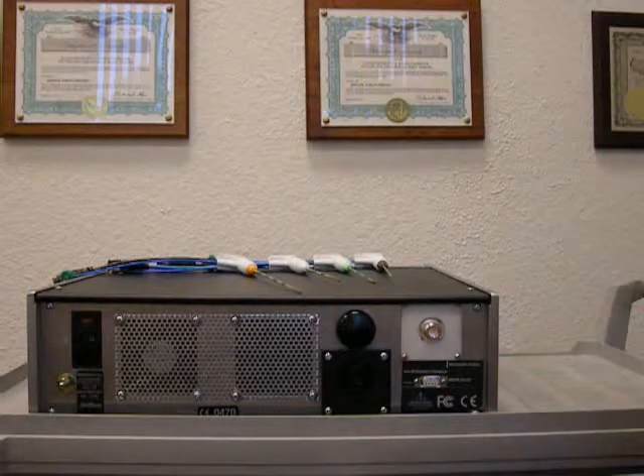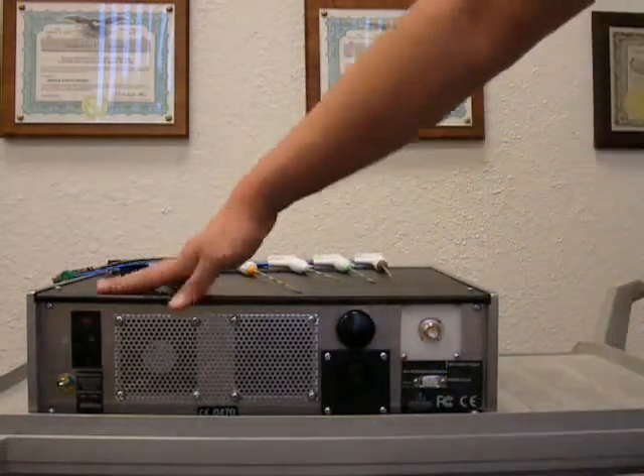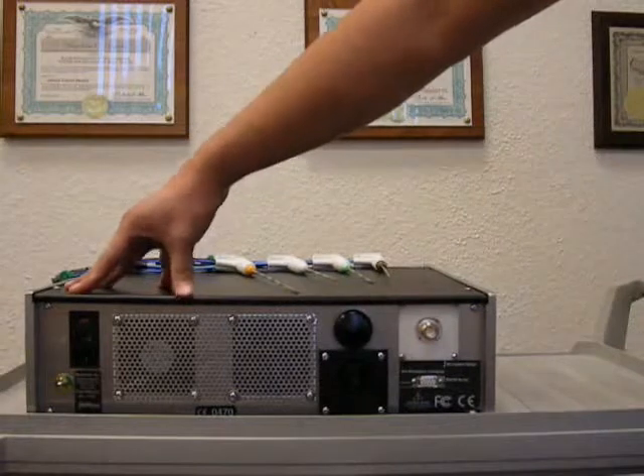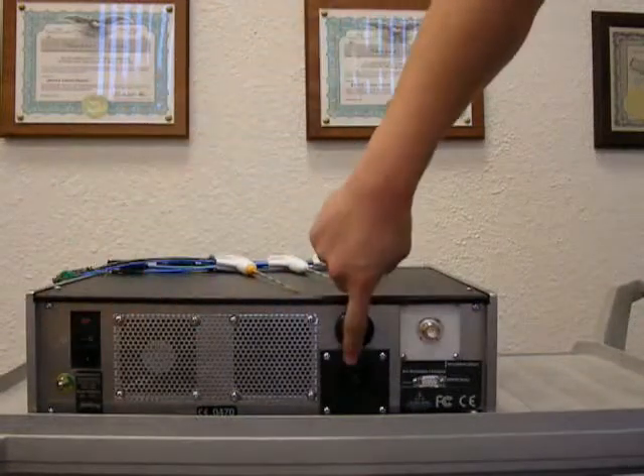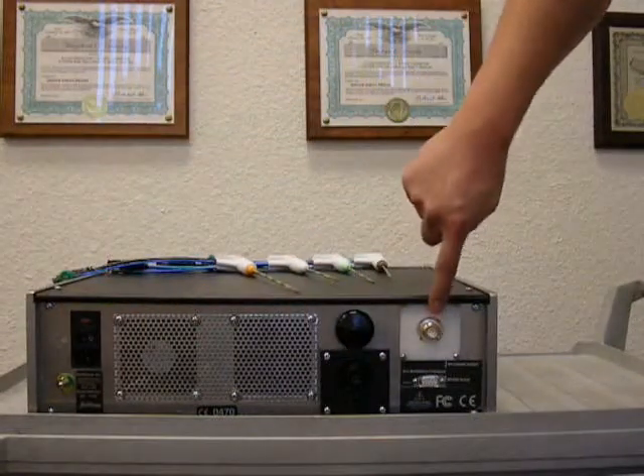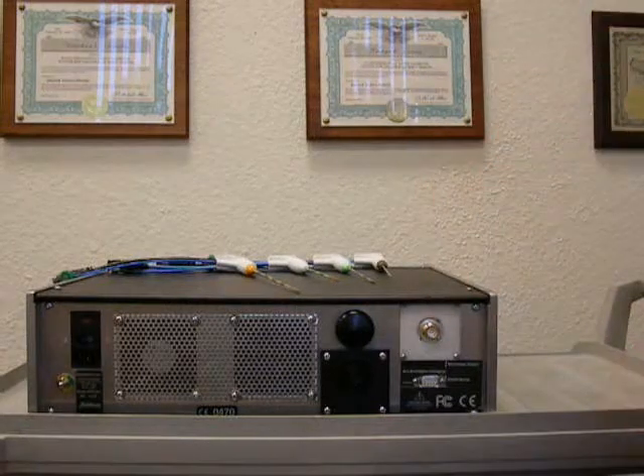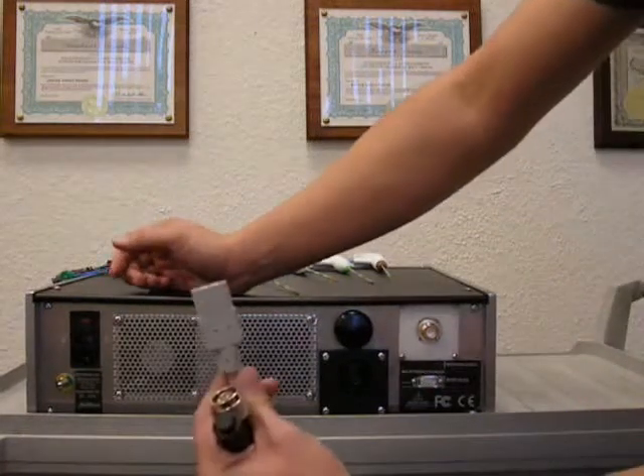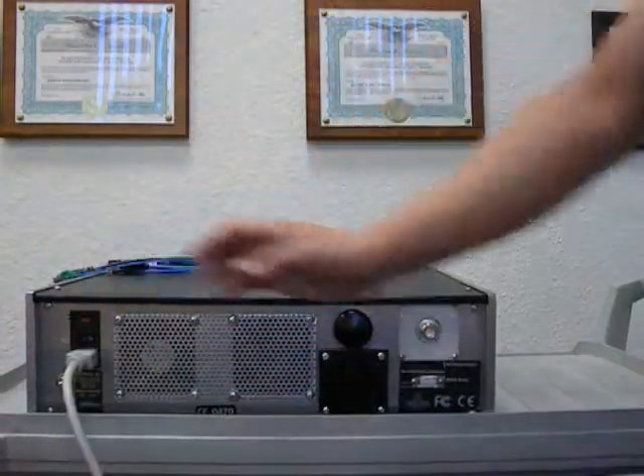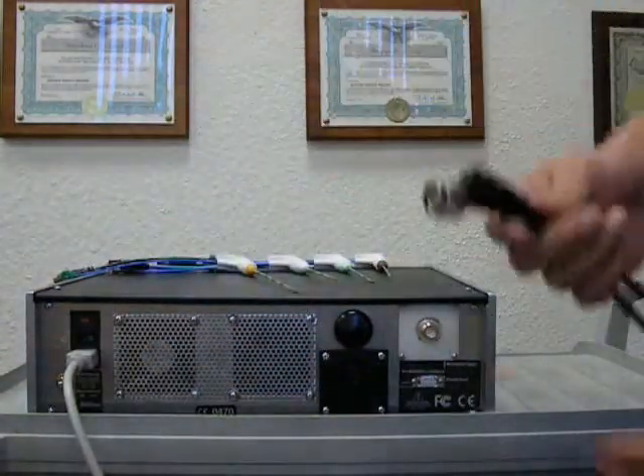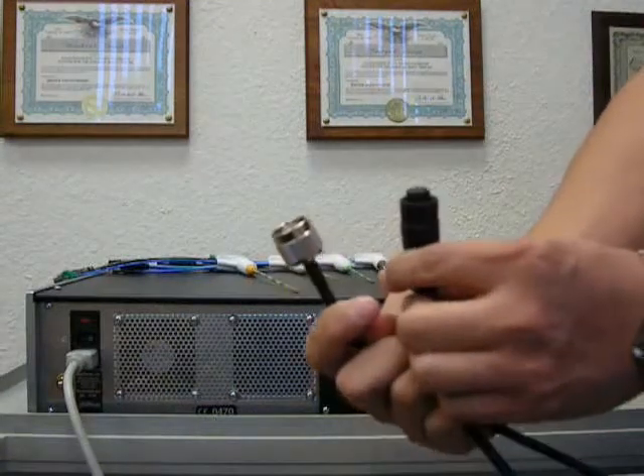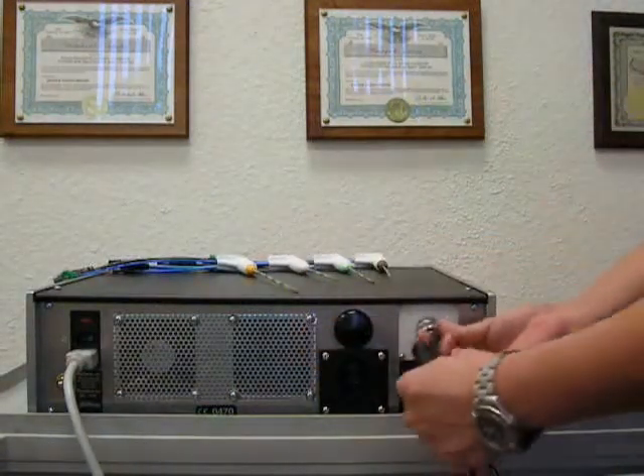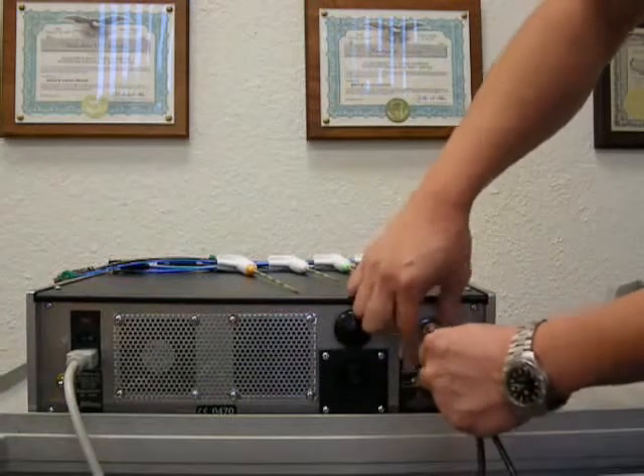This is for the setup of the generator. As you can see, this is the back. There are three connections, one for the power, one for the signal cable, and one for the RF cable. To start, you want to connect the power extension cable into here. For the extension cables, you want to find the end that looks like this. Connect the power cable into here and just twist until it stops.